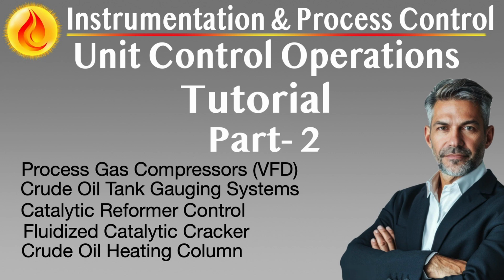Wet gas compressor, WGC, control is another vital part of FCC operation. As the primary gas handling equipment for cracked products, the WGC must maintain stable suction pressure and protect downstream recovery units. VFD-controlled compressors or steam turbine governors are managed via anti-surge and load-sharing logic, often coordinated with overhead vapor flow from the main column. These compressors now integrate with unit-wide APCs to adjust for feed swings, hydrogen content variation, or load-shedding events during flare system saturation.